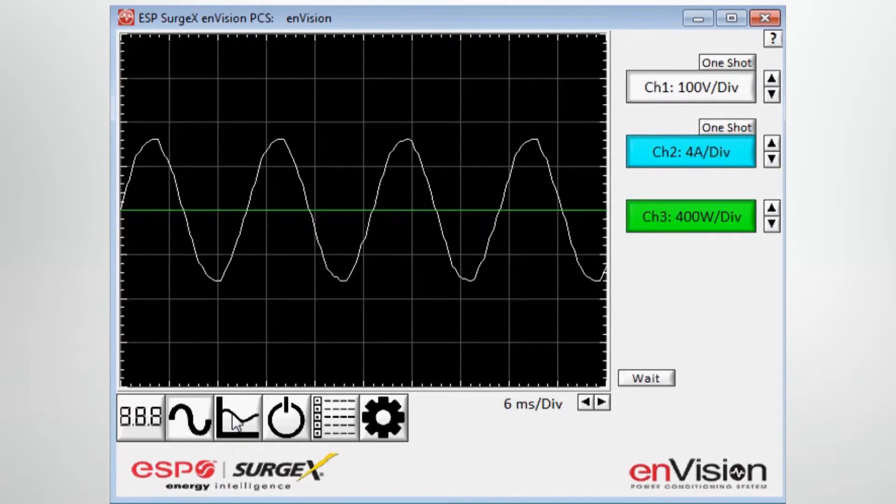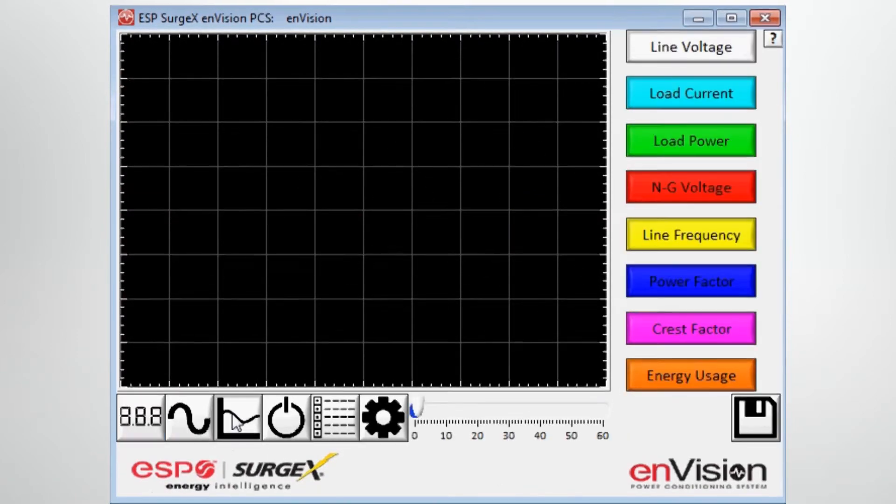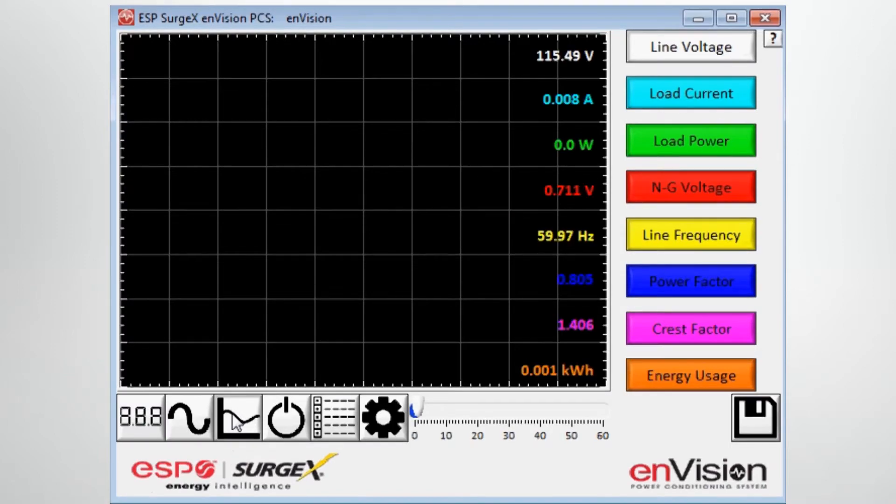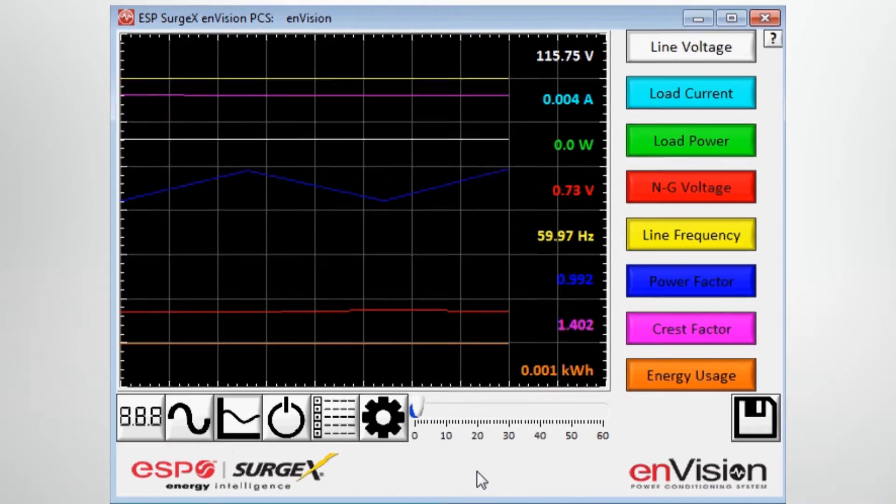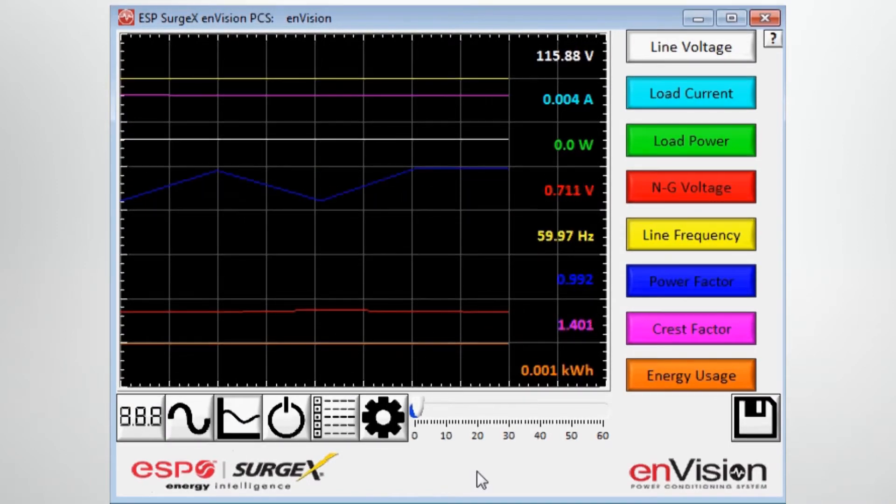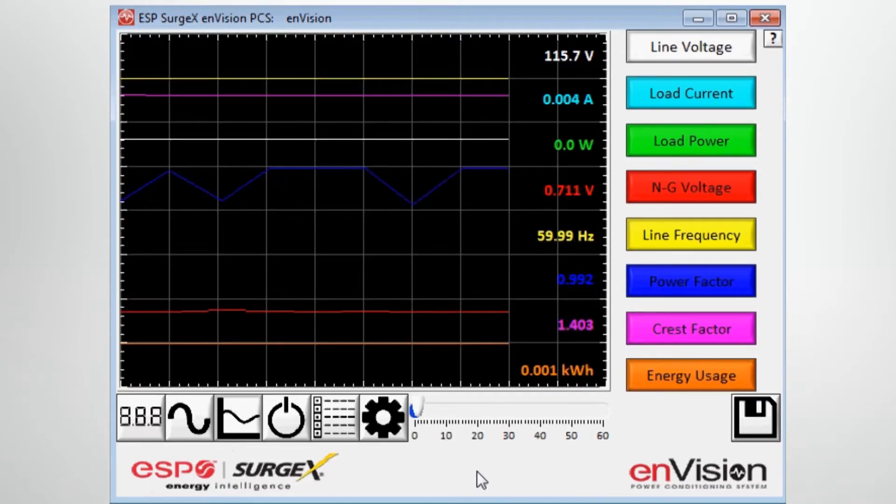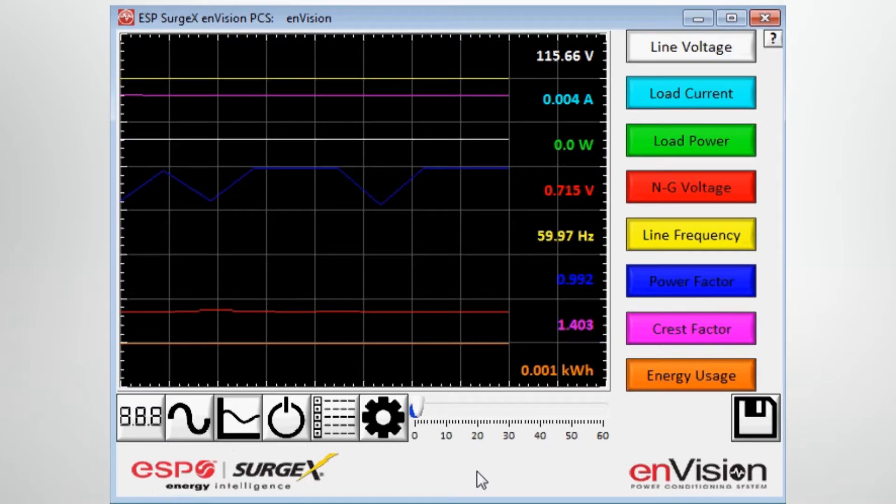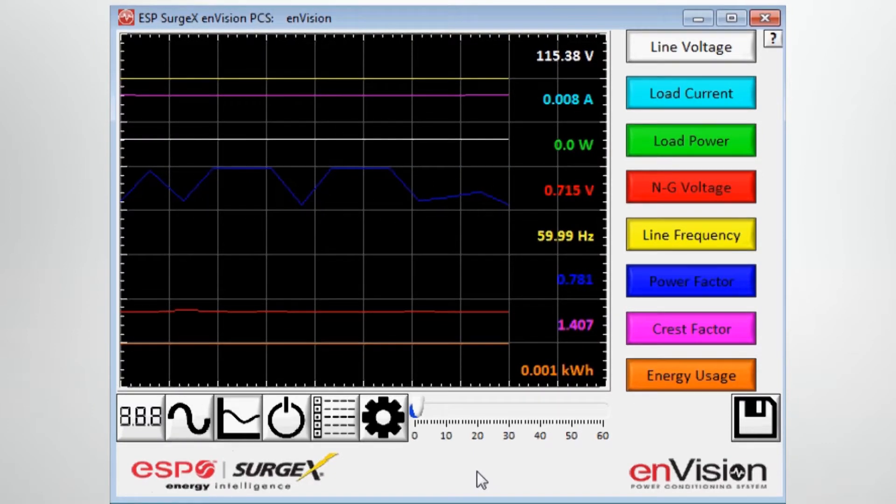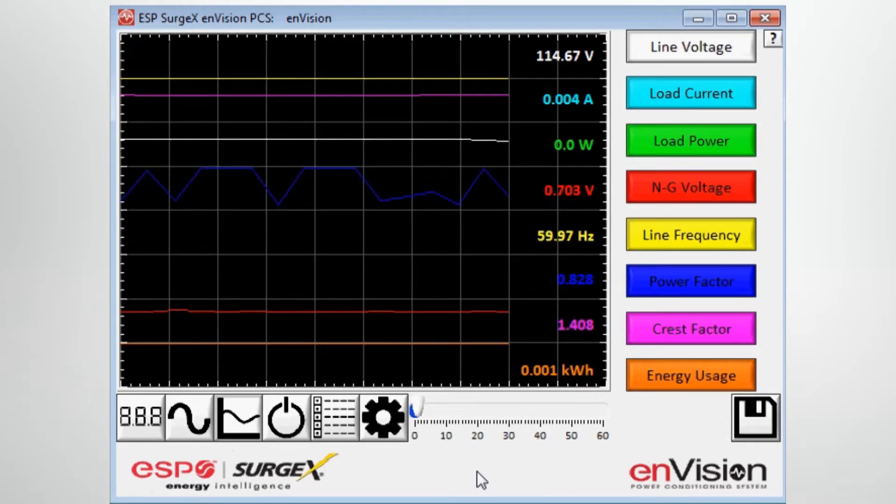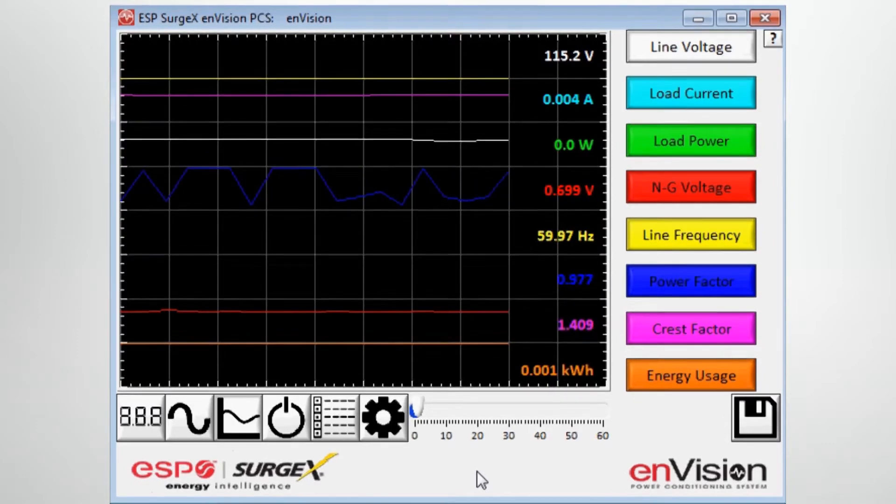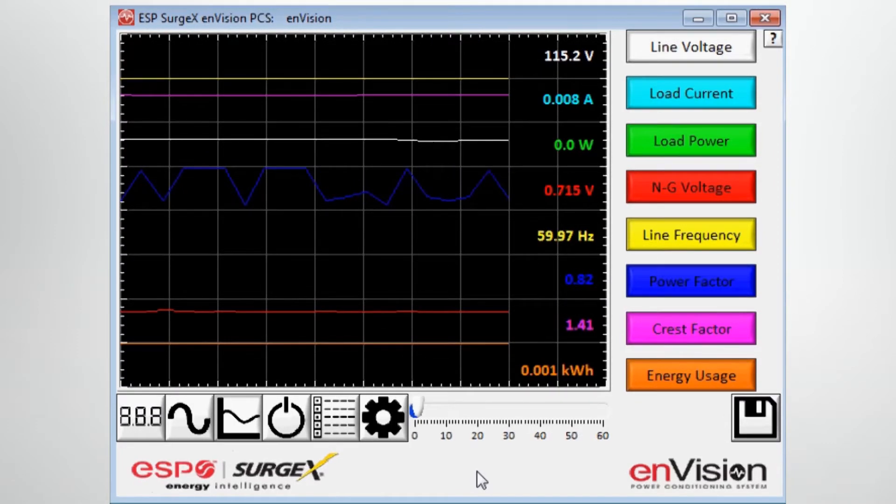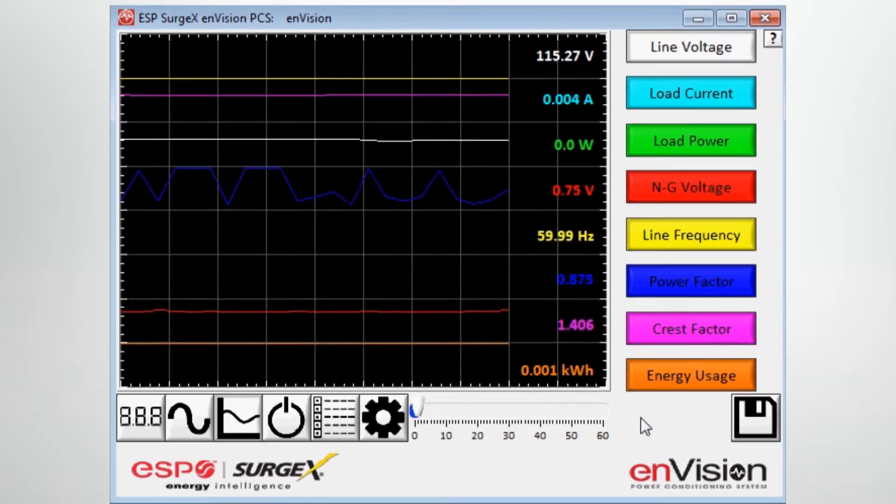Moving on to the next button, it's chart mode. In chart mode, you have access basically to all the parameters on the front multimeter page but in a graphical format, chart format. Basically, what you're seeing here is a live representation of all those parameters: line voltage, load current, load power, neutral-to-ground voltage, line frequency, power factor, crest factor, and energy usage, as they are occurring in one-second intervals.